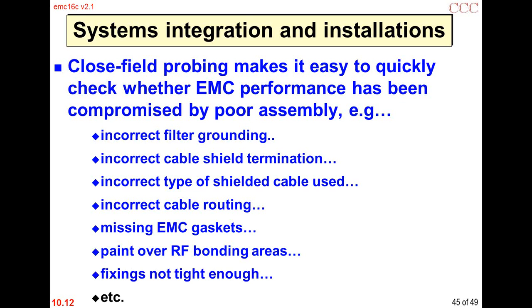Because nearly all our electronics these days are noisy - digital circuits, switch mode power converter circuits - it's very easy to check just with a spectrum analyzer and a close field probe, even a handheld spectrum analyzer and probe. You can very quickly check whether the system has been integrated or installed properly, if there are bad cables, wrongly terminated shields, or improperly mounted filters. It takes a few seconds to hold the probe against something and say, oh look, there's a problem here.